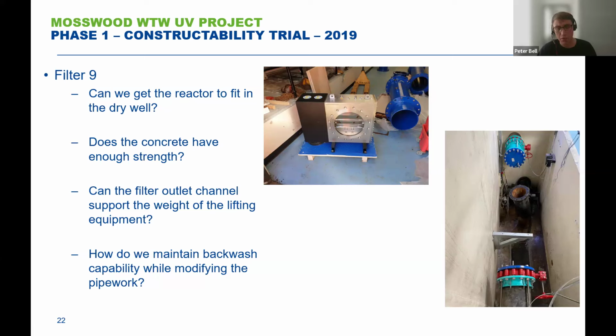The actual filter outlet channel, which you can see in the top picture, that is the filter outlet channel soffit. Underneath there flows 130 meg of water on average. It's about 1.6 meters deep underneath there. It's an enclosed channel, but we had to bring a lot of equipment across the top of there, so we had to understand whether that channel was capable of taking the weight of the equipment used to install it. So we had to do a lot of concrete tests on there to make sure that we understood the integrity of it, to make sure that it was safe to take this load. The loads were up to around 700 kilos in weight. Most of that was through a bespoke-made, manually operated crane unit that was portable. What that allowed us to do was to lower the equipment down into the dry well safely, without the need for major block and tackles being attached to the ceiling above us, and we could then move that around quite easily.